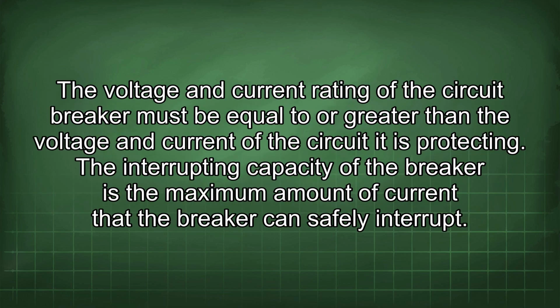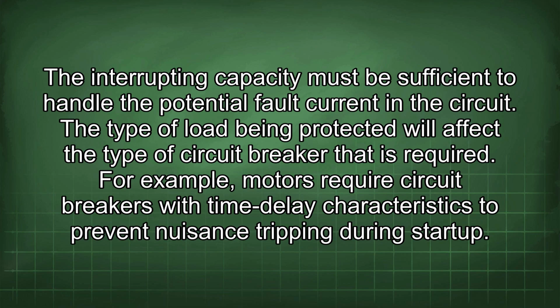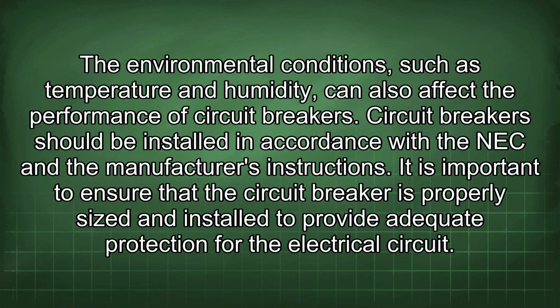The voltage and current rating of the circuit breaker must be equal to or greater than the voltage and current of the circuit it is protecting. The interrupting capacity of the breaker is the maximum amount of current that the breaker can safely interrupt. The interrupting capacity must be sufficient to handle the potential fault current in the circuit. The type of load being protected will affect the type of circuit breaker that is required. For example, motors require circuit breakers with time delay characteristics to prevent nuisance tripping during startup. The environmental conditions, such as temperature and humidity, can also affect the performance of circuit breakers.